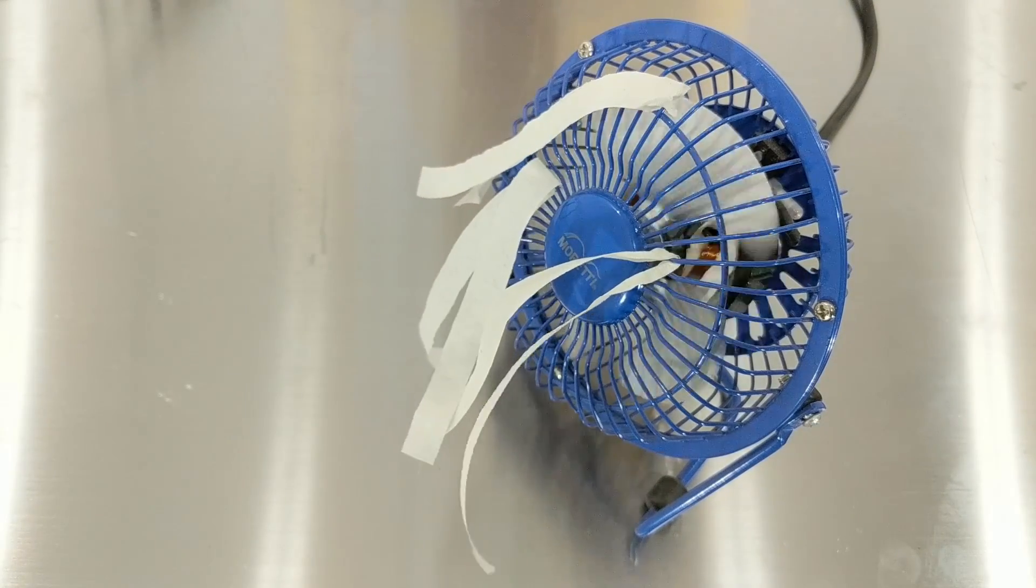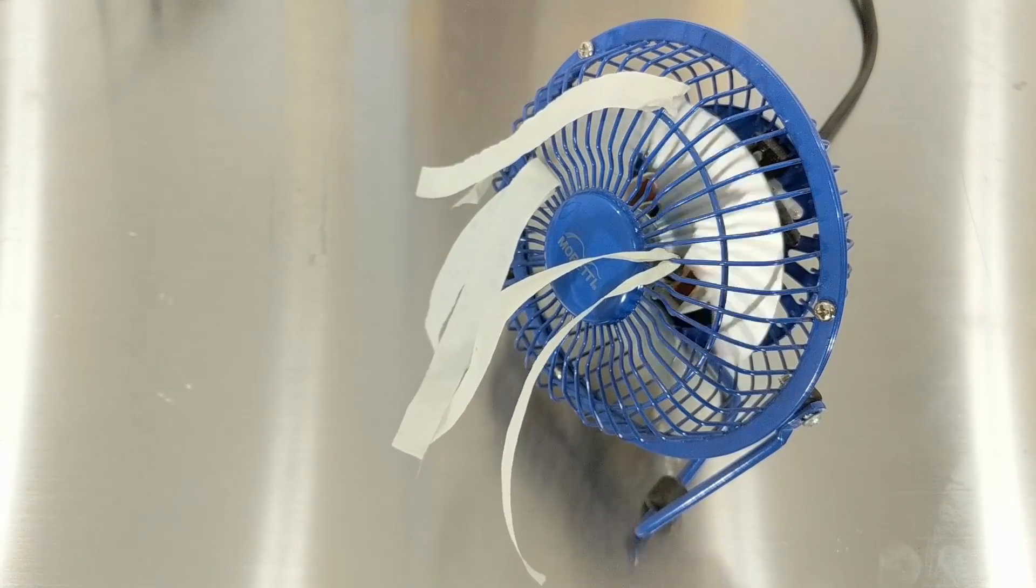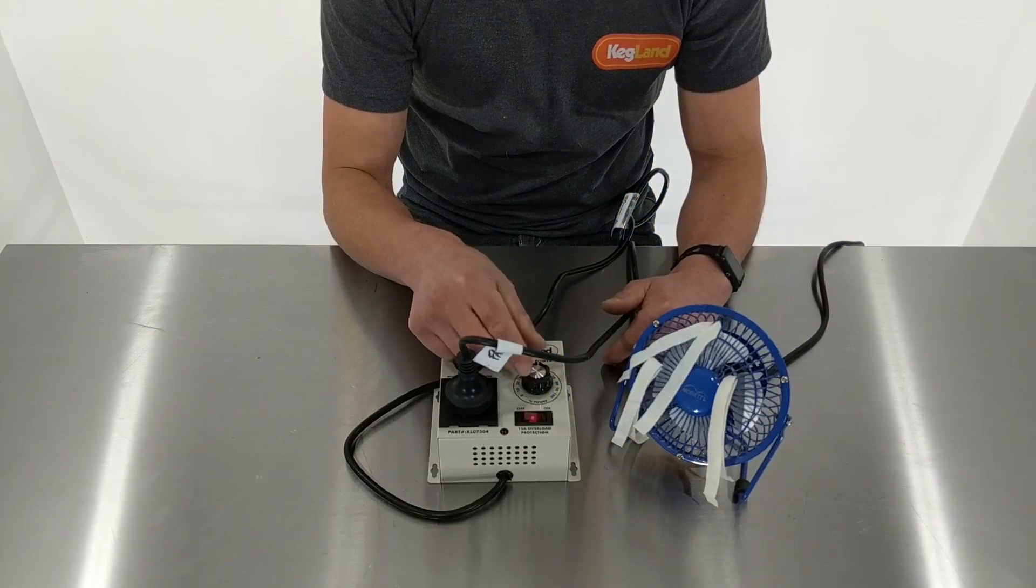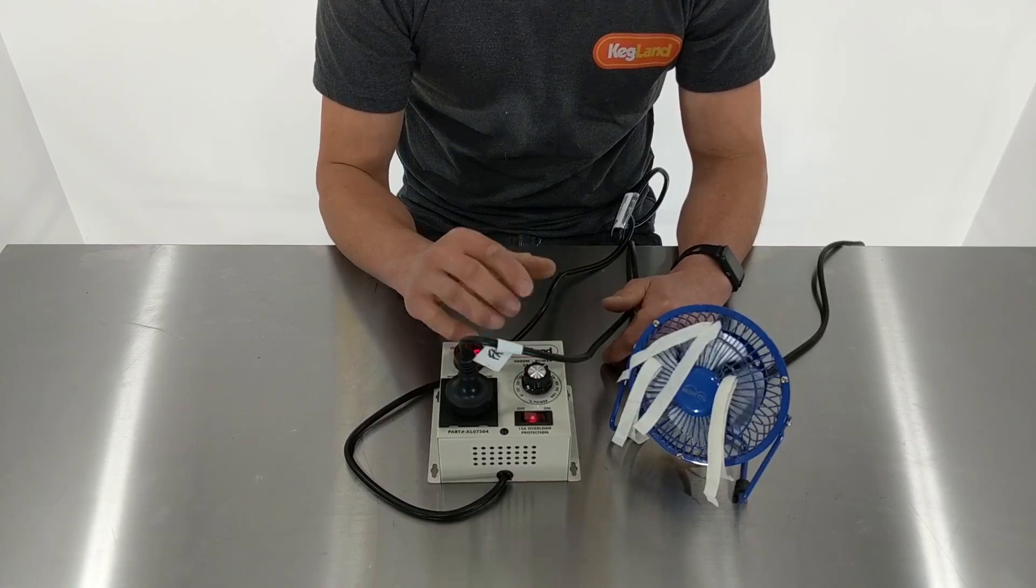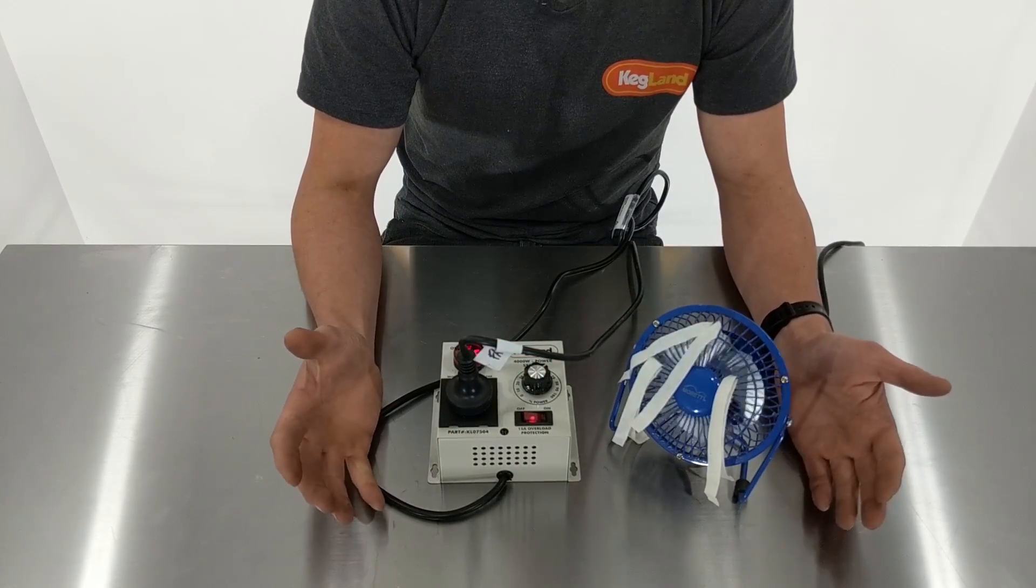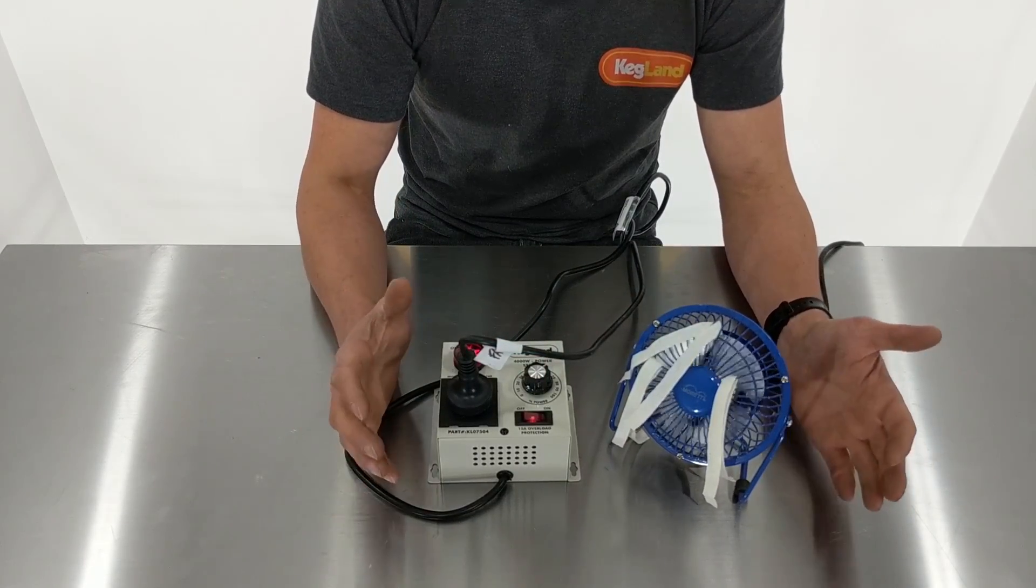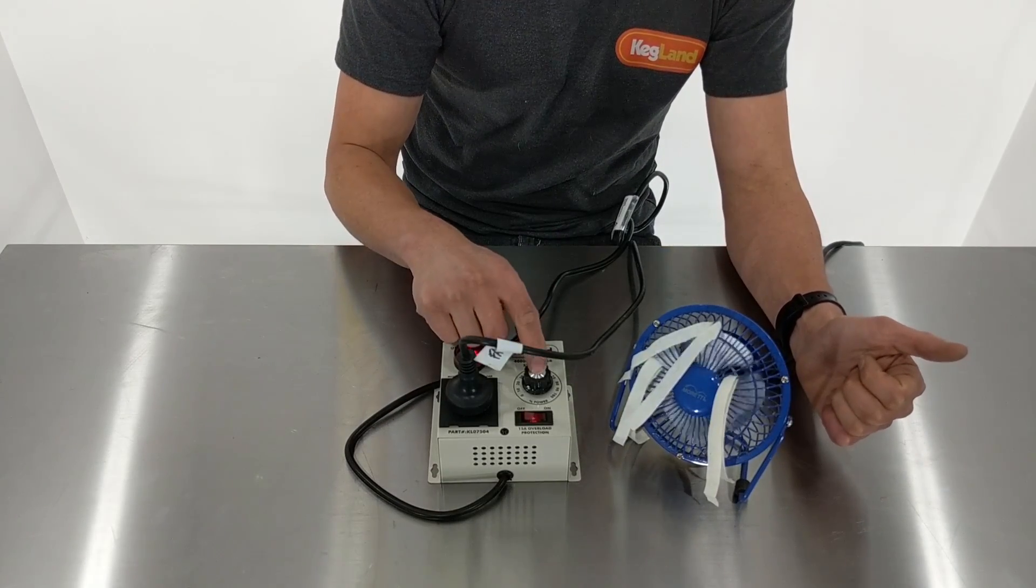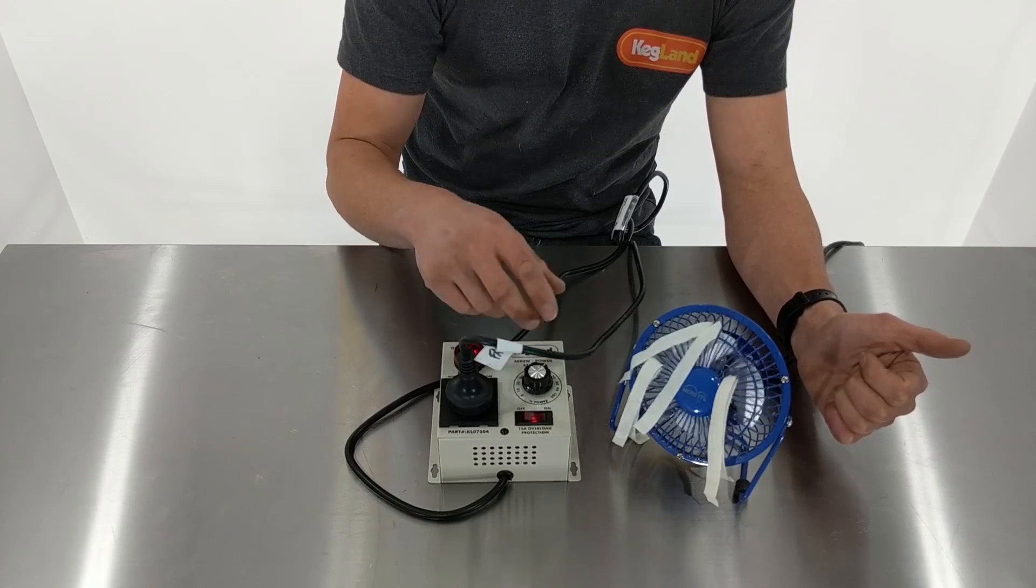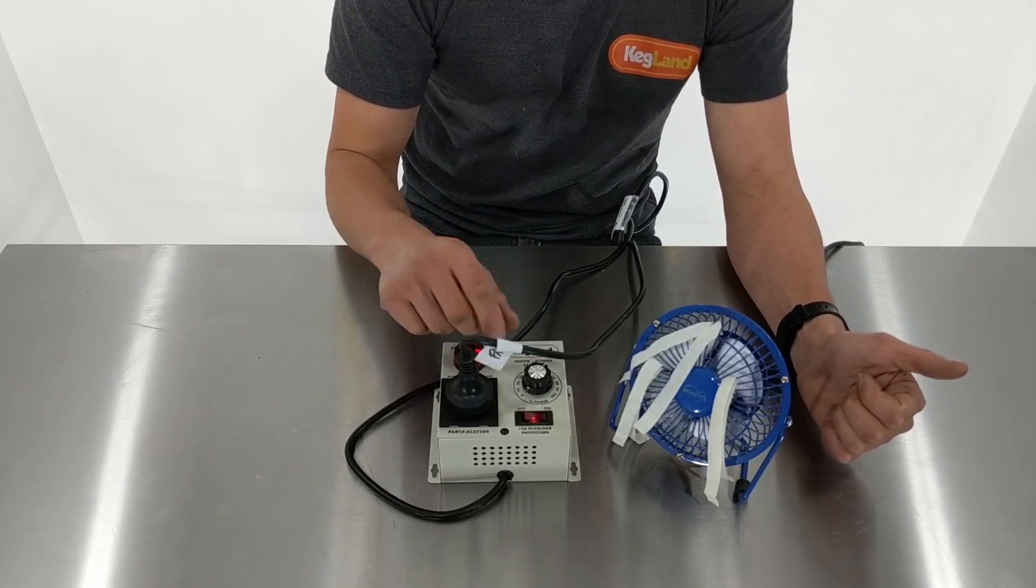Now one thing you don't want to do with motors is go too slow. So I wouldn't want to go right down here and just stall it because eventually that can cook the fan. So you always want to make sure with motors - if you're going to use this for a grain mill for instance, which might be a really handy application if you want to adjust the grain milling speed - always make sure on the controller you're using a minimum speed to actually get the motor turning. That's obviously a really important part.